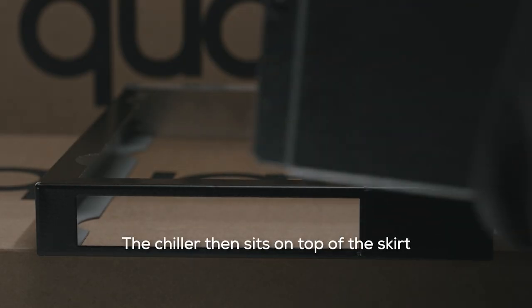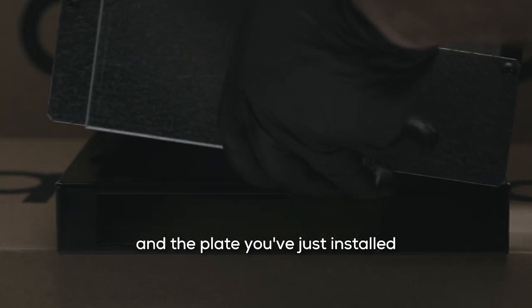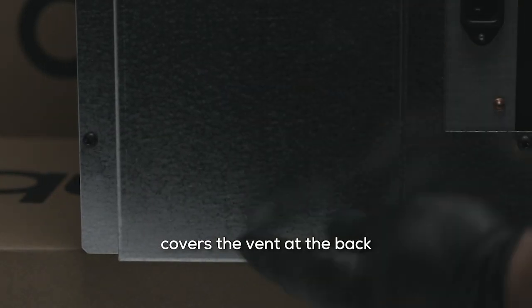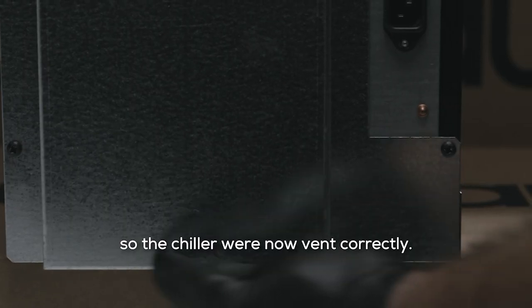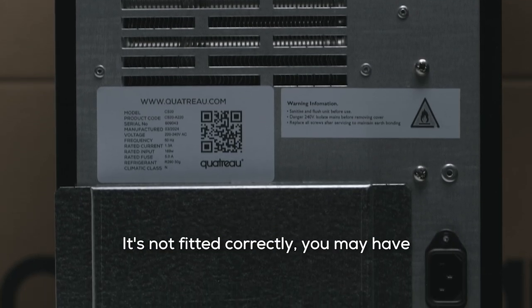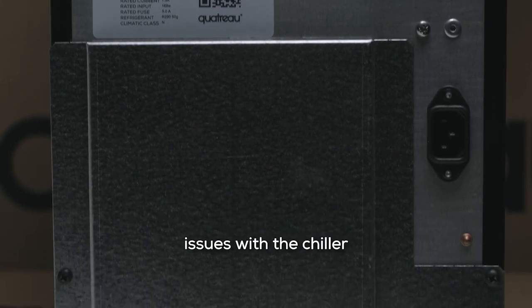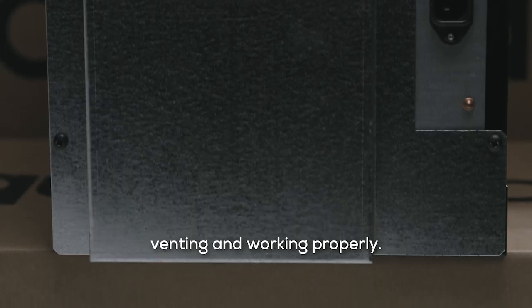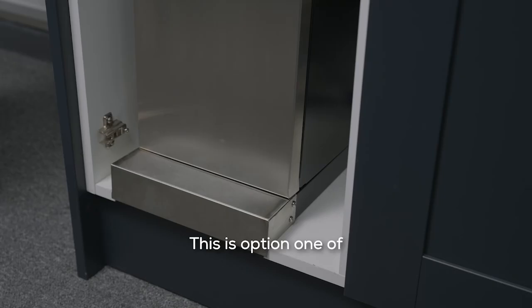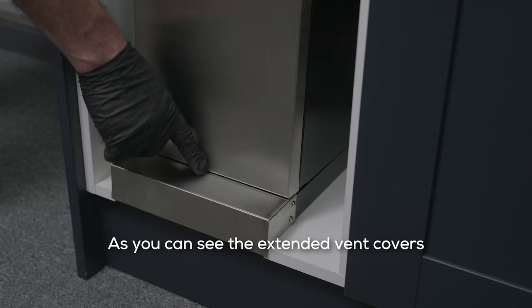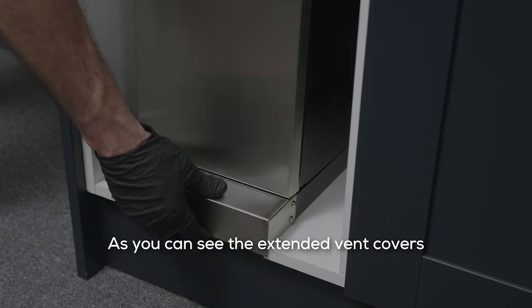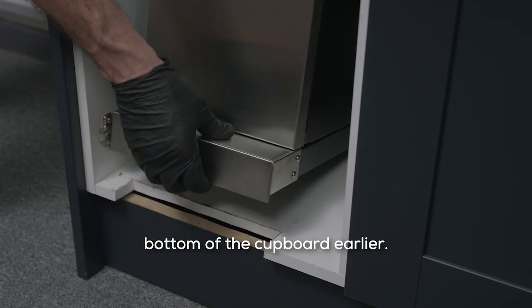The chiller then sits on top of the skirt, and the plate you've just installed covers the vent at the back, so the chiller will now vent correctly. If it's not fitted correctly, you may have issues with the chiller venting and working properly. This is option one of the chiller vent kit. As you can see, the extended vent covers the hole you cut in the bottom of the cupboard earlier.